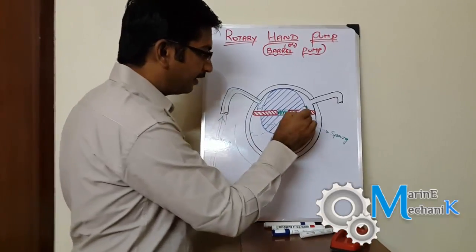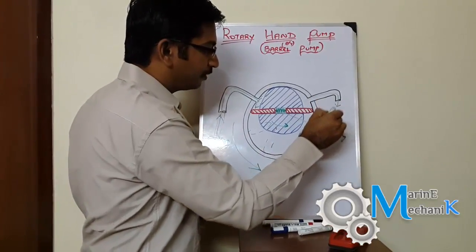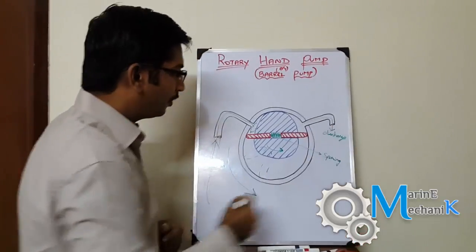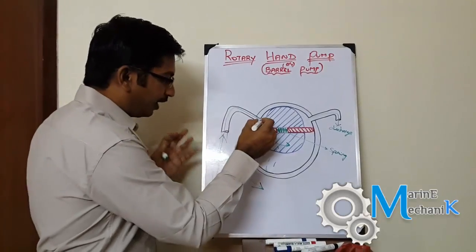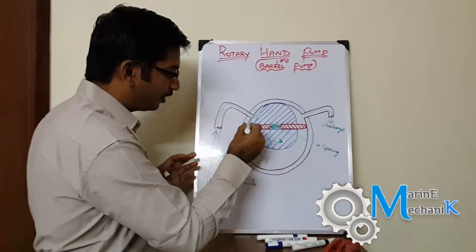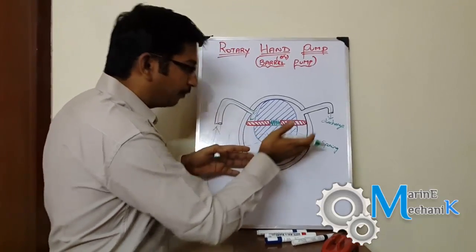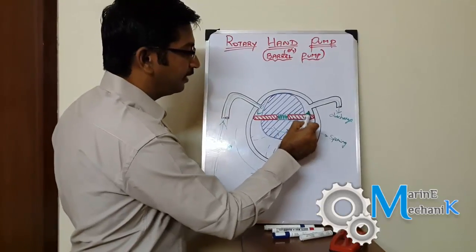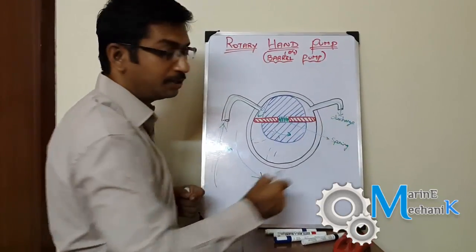Then it goes to this channel, which is the discharge. The vane traps liquid between this space, and as it rotates, it travels through the pump chamber. Then as the vane is getting compressed on the other end, it goes out to the discharge port.